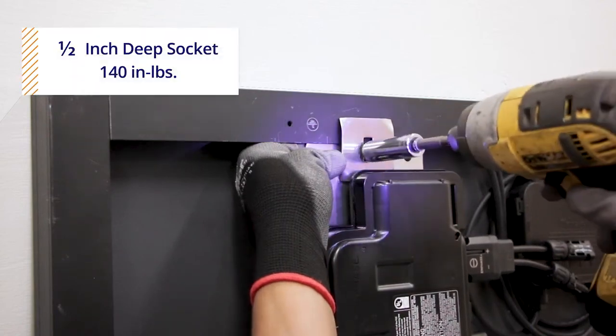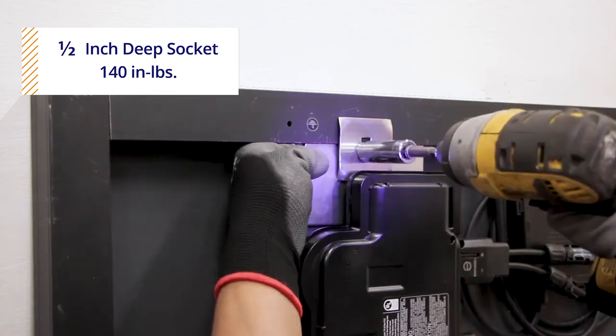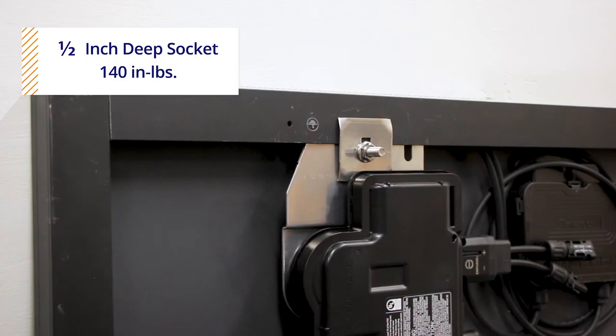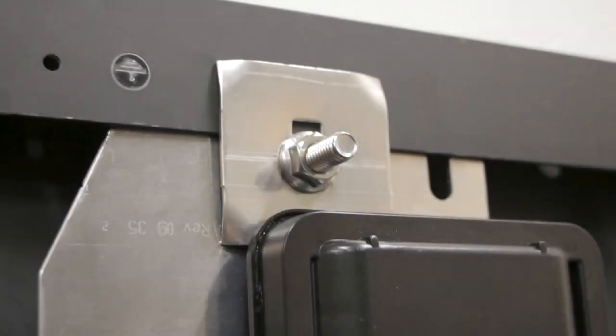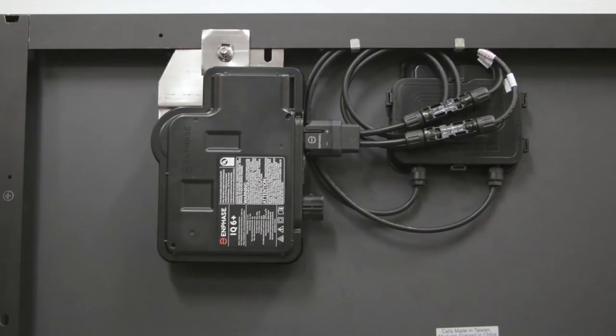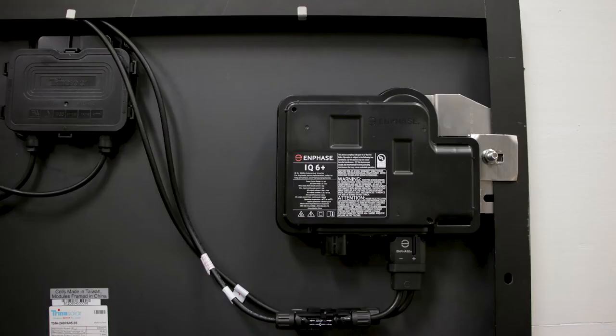Using a 1/2-inch deep socket driver, secure the clip to the module frame by tightening down the nut to 140 inch-pounds. The bent corners of the clip need to be biting into both the outside of the module frame and the inverter flange to ensure proper bonding.